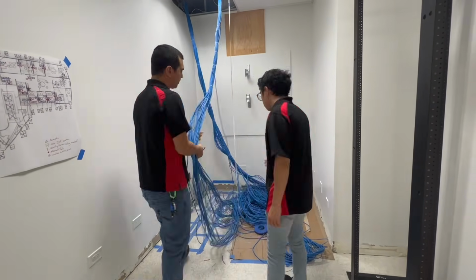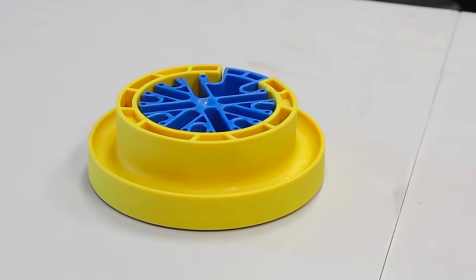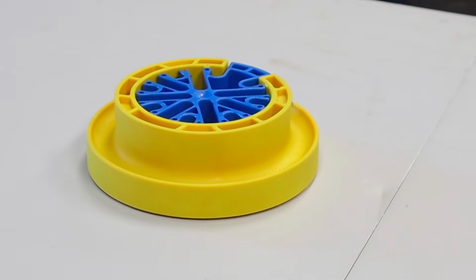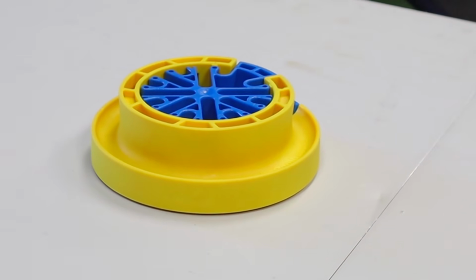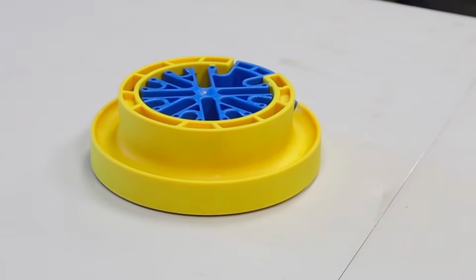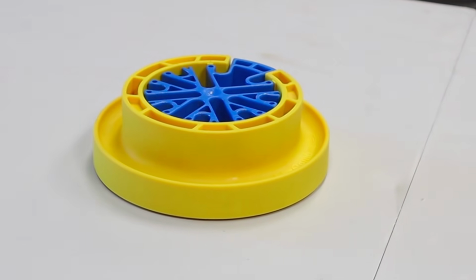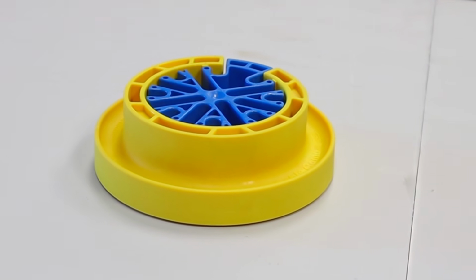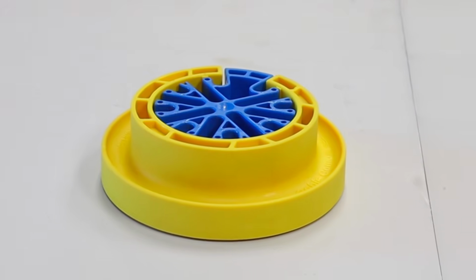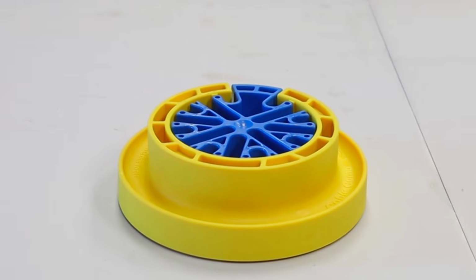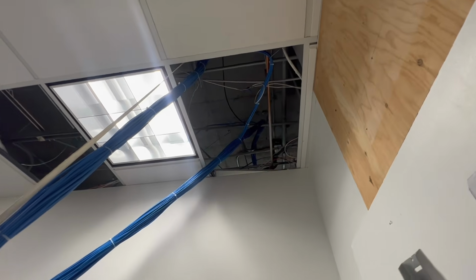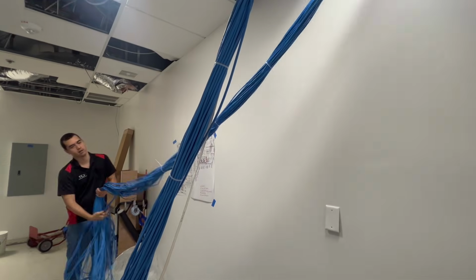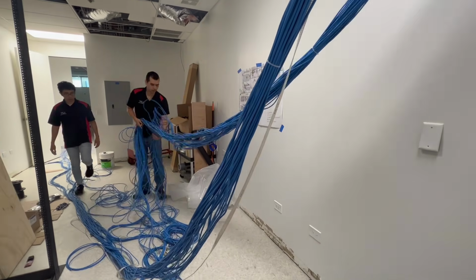Our primary sorting tool is the cable comb, meant for 24 cables of Cat 6 diameter. You lay all the cables into this honeycomb shape and slowly pull it down, untangling as you go and Velcroing every so many inches. We've settled on a 12-inch Velcro strategy, and we'll just go ahead and pull this through.